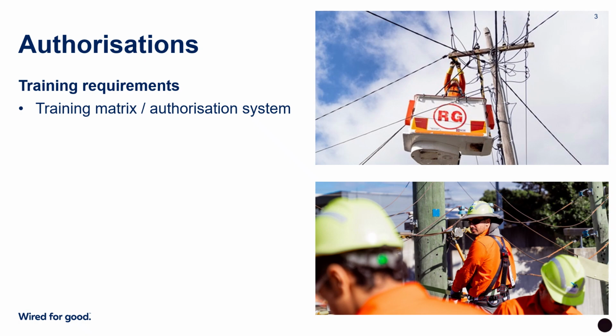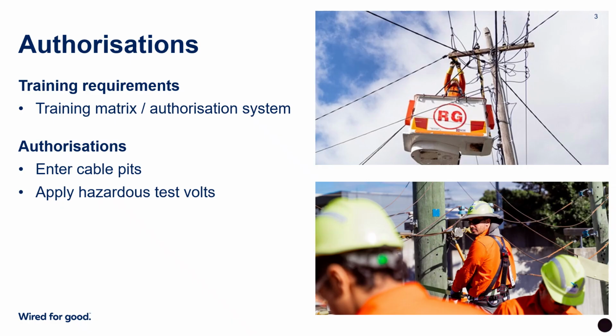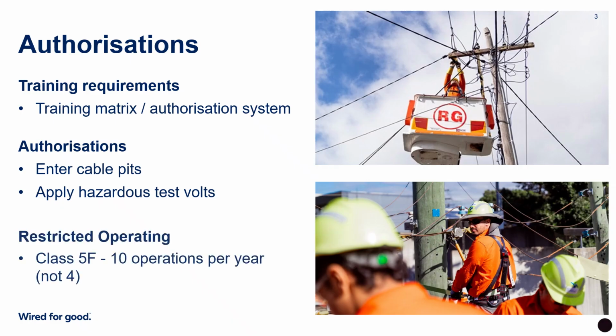Training requirements for the various authorisations required by the electrical safety rules have been removed and replaced by references to the Ausgrid training matrix and/or authorisation systems. The authorisations to enter cable pits and apply hazardous test voltages have been included in this edition. To maintain their authorisation, Class 5F restricted operators are now required to use their operating authority at least 10 times per year instead of the previous 4 times per year.